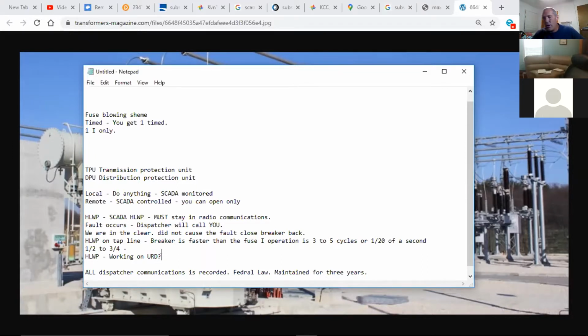If you go inside a transformer or cabinet where you actually need to get up close, you might need to put a blanket down and manually handle it—you're going to need a hotline work permit. But if I need to pull an elbow off a transformer, put it on a parking stand, or put it on a feed-through, we do not require a hotline work permit because there's really no exposure. Robbie, what do they do? Same thing—anything like that inside a pad, no hotline work permit. The only time we do it is if it goes from overhead to underground, a riser pole with no switch up there, and you have to go up and mess with it hot.